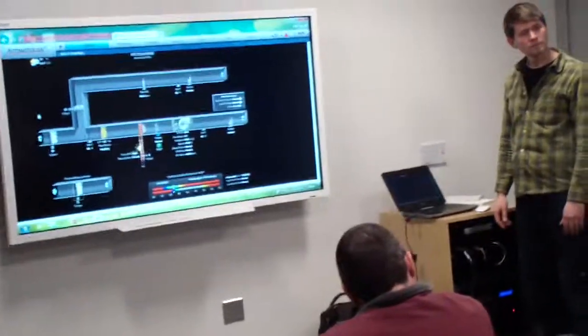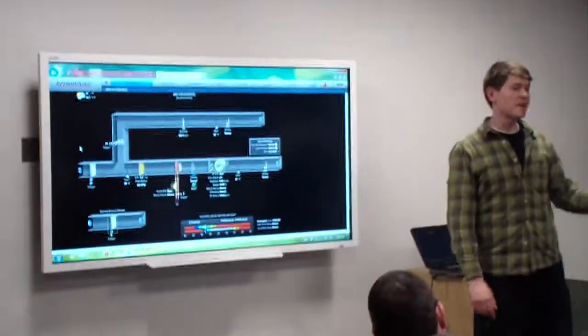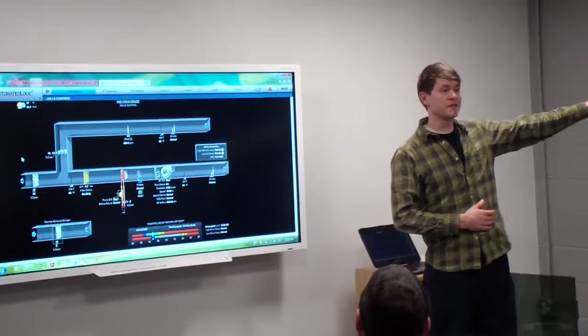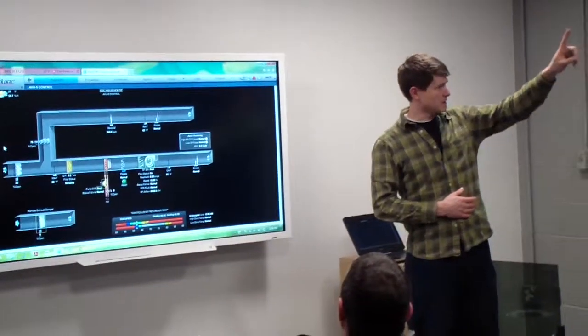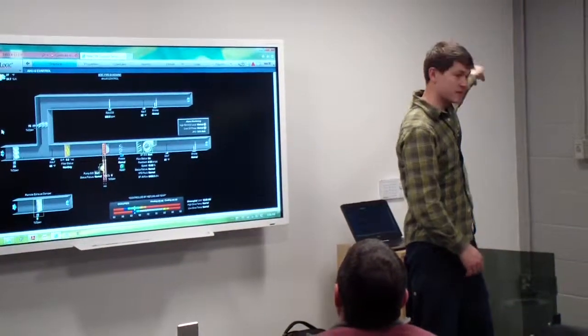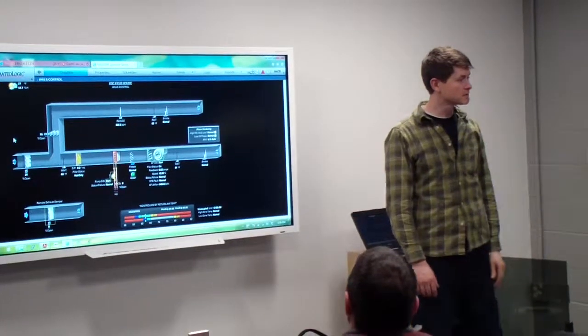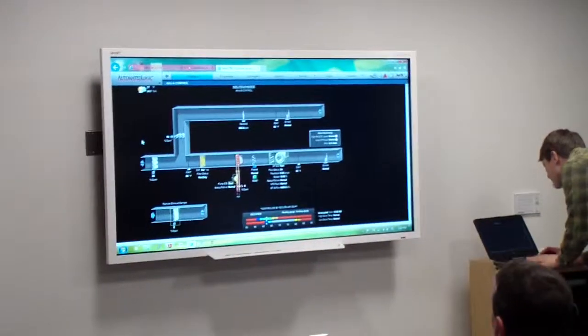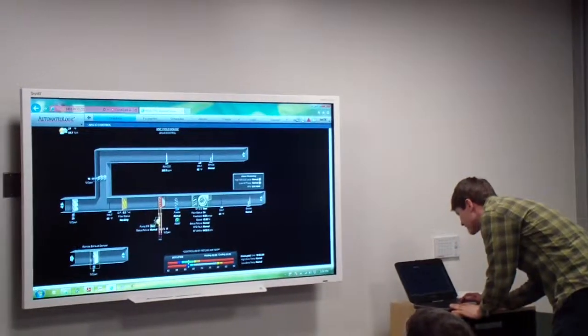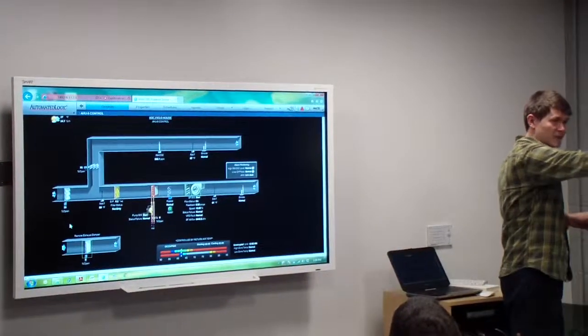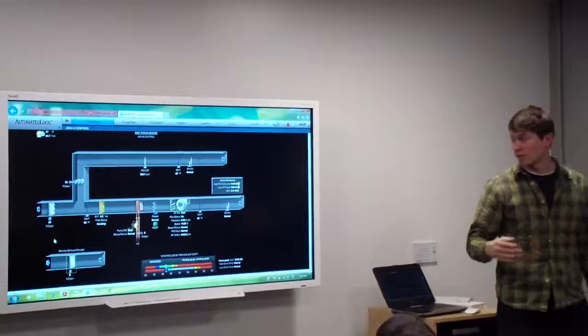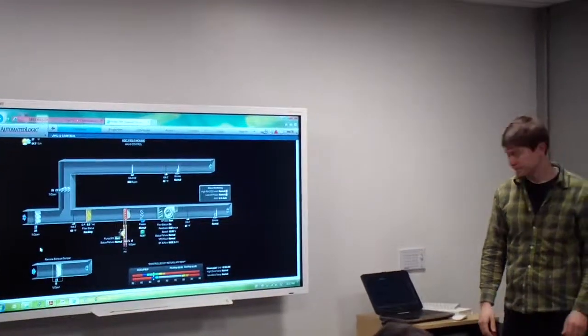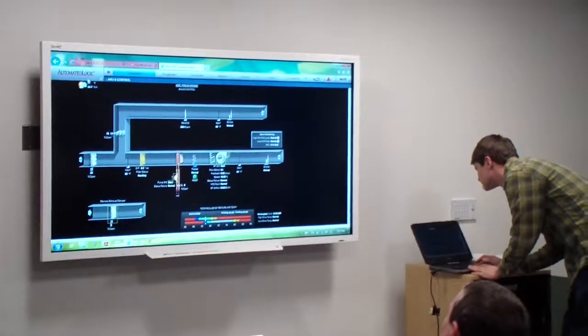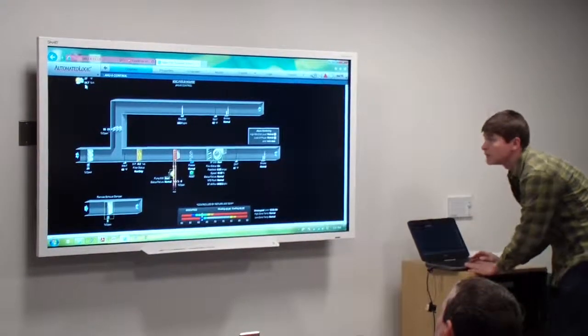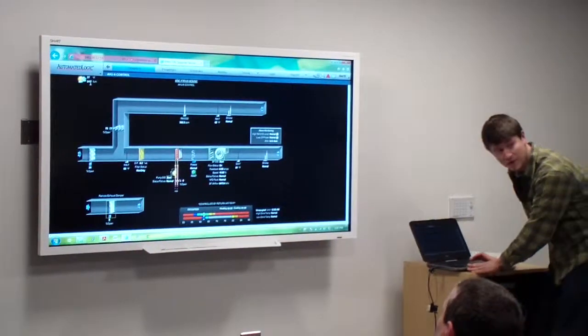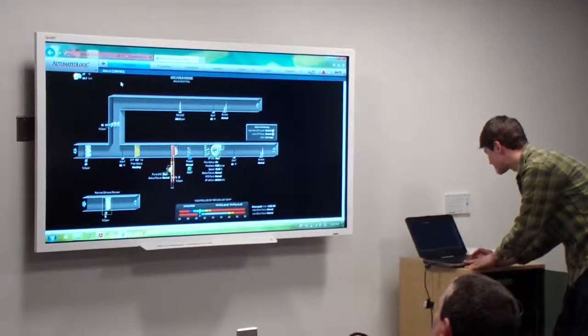Did you say what does that air handler serve? I'm sorry. So air handlers 5 through 8, which are the next 4 that I'm going to show, those are the field house air handlers. I believe our closest one is 5, 6, and then 7 the closest one on the left side, 8 the further one back by the garage doors. I believe that's correct. And the exhaust damper? Yep, and then this is the external dampers, which are the dampers on the right side of the building, by the street. Those 4 are run through these controls. And you'll notice, as we see here, you've got your outside air temp and your outside air humidity. Now that shows up on every page, so you can always know what the temp is outside.